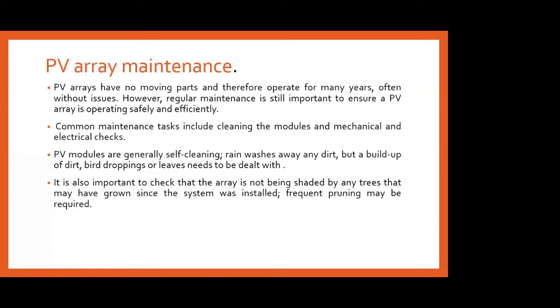Coming to the next part, PV array maintenance itself. That is the first and important thing here, and we have to take care of the maintenance of the PV arrays. Of course, PV arrays don't have any moving parts, so the operating period of PV arrays will be many years without any issues. But regular maintenance has to be done for your PV arrays, which includes cleaning the modules.